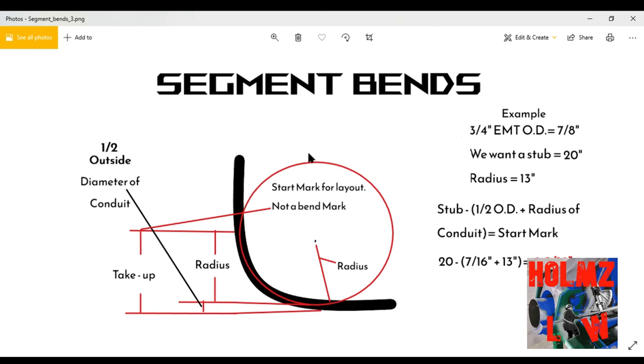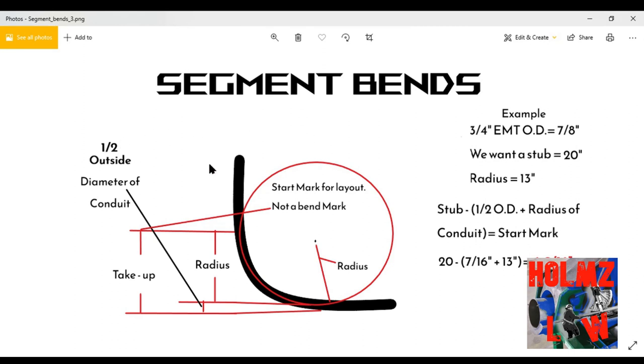Now this is important — the radius. Most bends you deal with involve a center and radius. Depending on whether you're counting the radius from the inside of your conduit or the outside, it makes a difference when doing a segment bend. When measuring for the radius, make sure you know whether you're measuring from the inside, outside, or centerline of it.